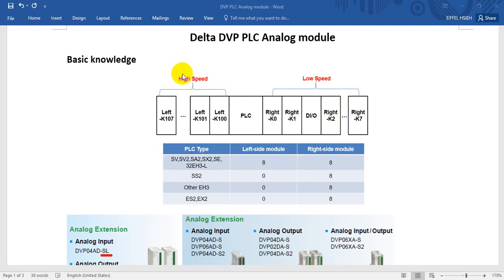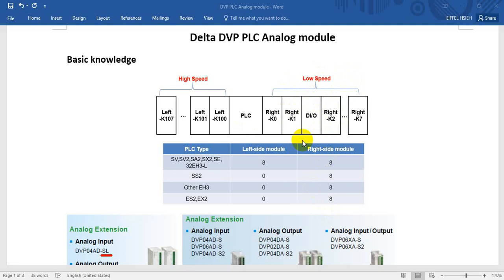You may wonder why I put high-speed and low-speed here. Basically, the left-hand side extension module is for high-speed, and the right-hand side analog part is for low-speed. For the right-hand side, for example, the analog input or output sampling time per channel is roughly 3 milliseconds. But for the left-hand side, it is around 250 microseconds. That is why I put high-speed and low-speed.